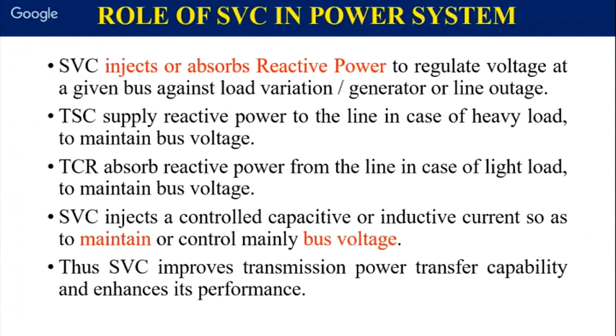This is due to the charge that is accumulated or that exists on the capacitors. You cannot switch on a capacitor just like that. It should be switched on at a point where minimum transients will be produced. So thyristor controlled reactors absorb reactive power from the line in case of light load to maintain bus voltage. Also, SVC injects controlled capacitive or inductive current so as to control mainly the bus voltage. It is mainly used for voltage profile maintenance.